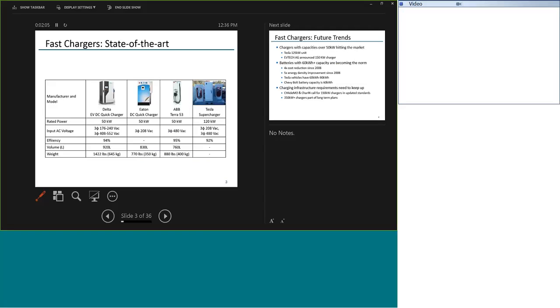So looking at the state of the art for fast chargers, you can see that the products currently on the market are typically rated at 50 kilowatts, and they connect to a three-phase 208 or 480 volt AC connection. The efficiency is somewhere in the mid-90s, not including the step-down transformer that takes the medium voltage distribution voltage down to the low voltage. The volume is somewhere above 700 liters and above 700 pounds weight. The exception is the Tesla supercharger that's rated at 120 kilowatts and is also connected to a three-phase low voltage supply, but has an efficiency of about 92%.